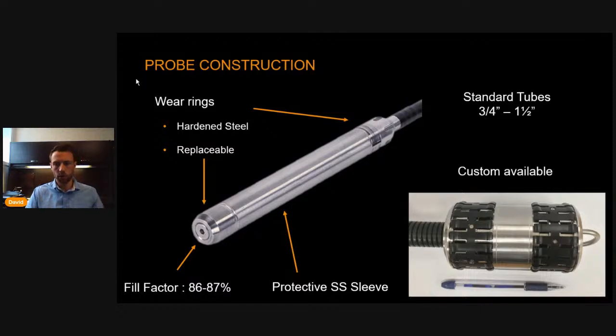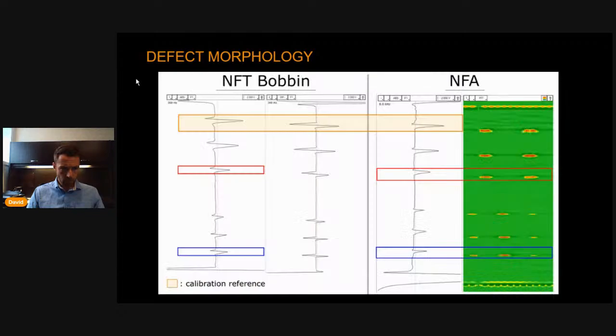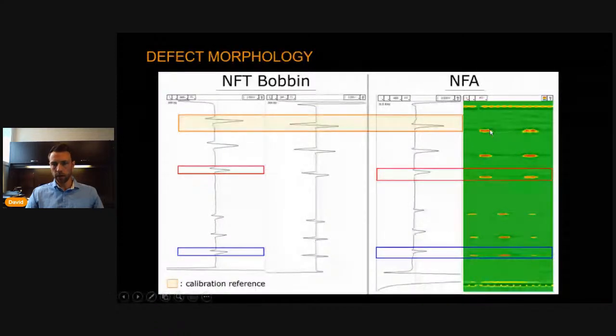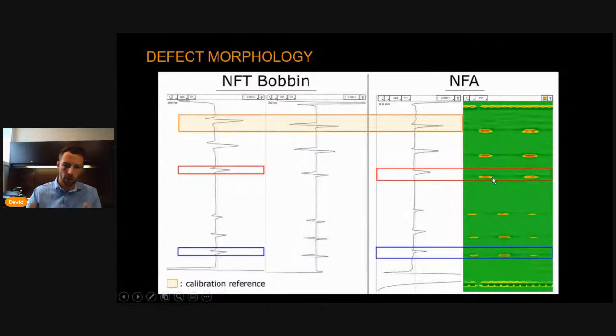This is one massive NFA probe that we designed just for one client. So this is something to keep in mind for special applications. Let's go back to the defect morphology. How does it translate to the NFA signal? Here is an example. We have near field on the left side and NFA, and you see that for a defect response like this, NFA will give you two very clear indications. That gives a lot more insight into what is going on in this tube. Same here at the bottom: those small indications are in reality 3 independent pits. So that's the value here. It's getting to know more.